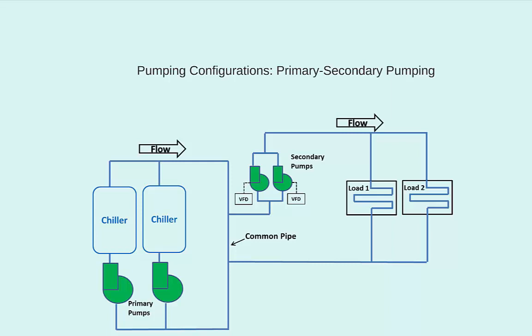First off, the pumps which serve the primary loop, that is the loop with the chiller or the boiler, are called the primary pumps. The secondary pumps are those located on the secondary loop, which sends water to the various loads. The reason for separating the hydronic system into two loops is to allow for variable speed pumping in the secondary loop, which we will show later on how that saves us a lot of energy, all while maintaining constant flow through the primary equipment. Maintaining constant flow through the primary equipment is a practice used to protect that primary equipment, and that concept will be further explained later in this course.